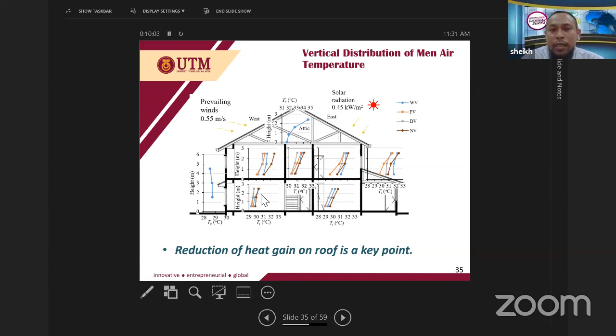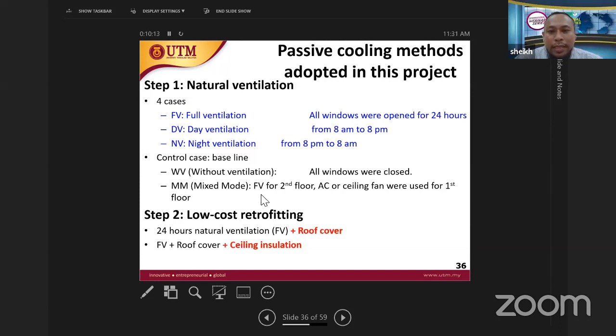So we can see here the vertical distribution of the mean air temperature for each room. We notice that near the attic, near the roof, the temperature is very high. So the key point here is that we need to reduce the heat gain from the roof, not from the side or the wall of the building. The main key point in the hot and humid climate of Malaysia is to reduce heat in the roof. That's why we conduct another measurement to propose the low cost retrofitting for cooling strategy.